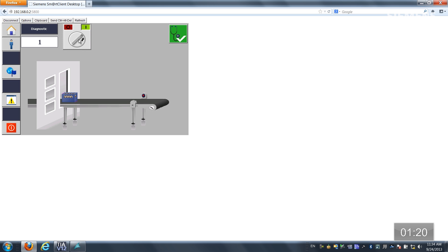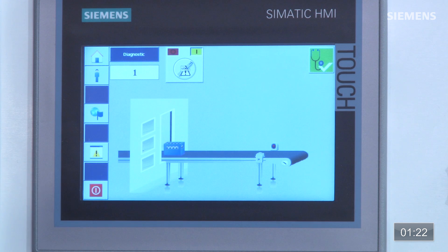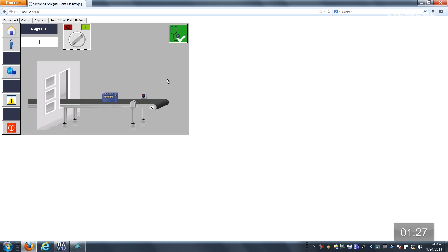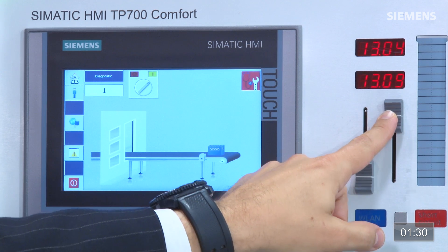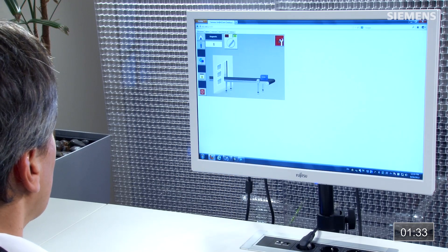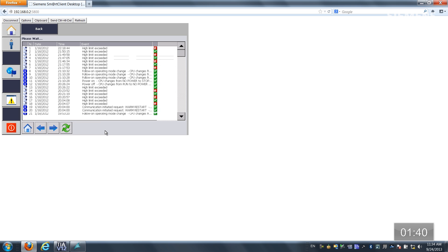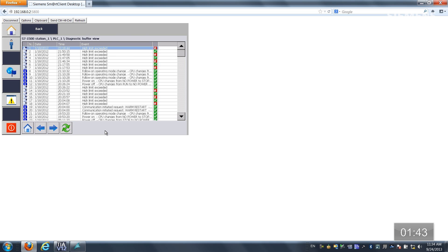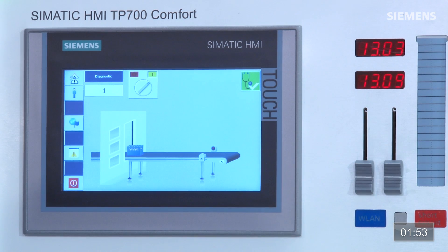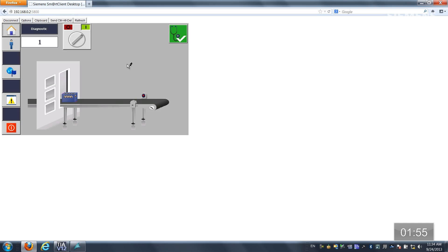I can come over here and turn it on — I do have Remote Control functionality. If I come over and move the slider, I can see that our actual beer bottle box is going across the conveyor. If I get to an end of travel, we actually get a fault. I can click on it and go straight to the ActiveX Control for Diagnostic Viewer window, click this button, and it will find exactly where the diagnostic is — a high limit exceeded. I can even drill all the way down to the actual point level in the hardware architecture to find where this fault is.